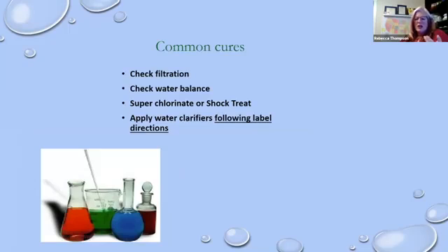Common cures, no matter what the issue is, check your filtration. If you have a cloudy pool, check your filtration. If you have algae, check your filtration. I went to a pool years ago where everything was perfectly balanced. The water was balanced. They had the right amount of sanitizer in their pool, but we could not clear this pool up. It was a sand filter. Took the multi-port off, stuck my hand down in there. I touched laterals. You should not be able to touch laterals in a sand filter. You should touch sand, and you should not be shoulder deep.